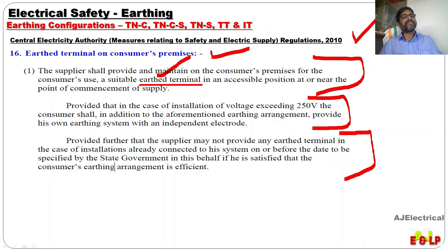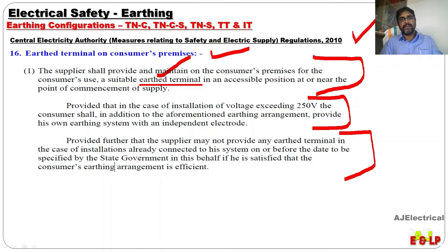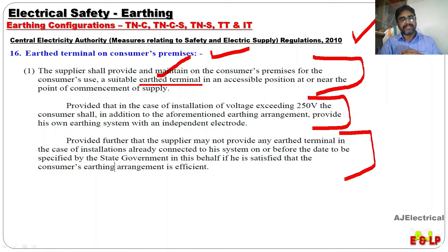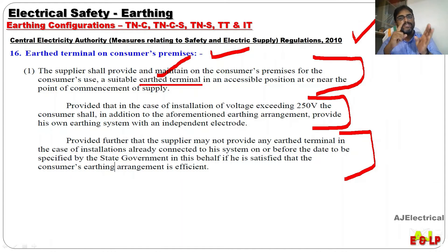See below that — another provision is there. It is said that if the licensee finds that the consumer's earthing arrangement is sufficient, they won't provide the earthing from the licensee or from the supplier. There is some missing word about the earthing configuration throughout this regulation — whether it is TN, or TT, or IT — that must be specified in this regulation. So we can expect that correction.